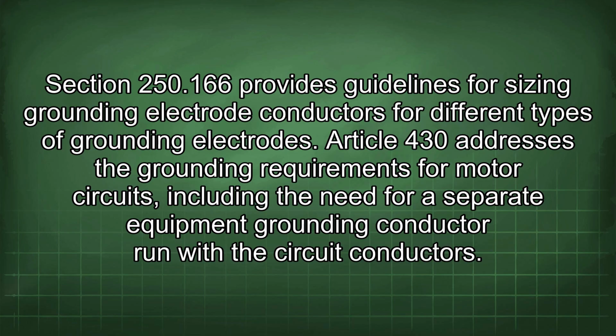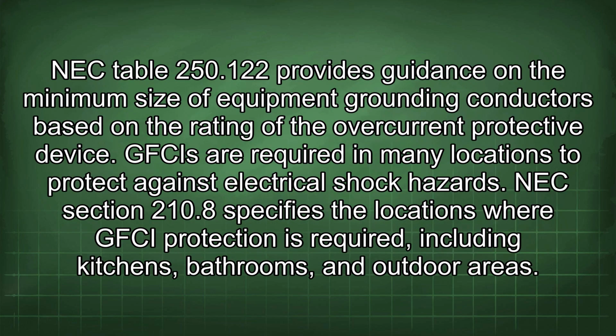Section 250.166 provides guidelines for sizing grounding electrode conductors for different types of grounding electrodes. Article 430 addresses the grounding requirements for motor circuits, including the need for a separate equipment grounding conductor run with the circuit conductors. NEC Table 250.122 provides guidance on the minimum size of equipment grounding conductors based on the rating of the overcurrent protective device.